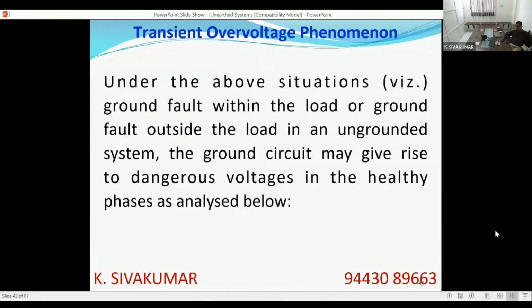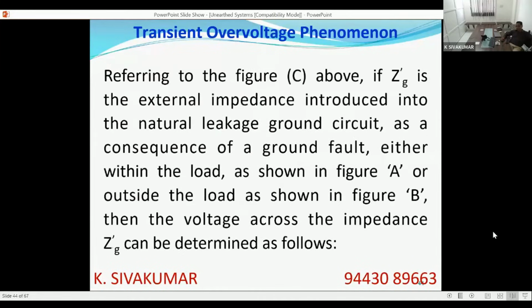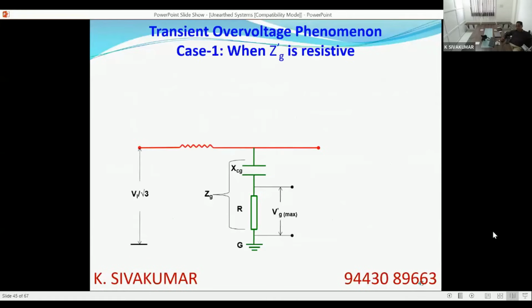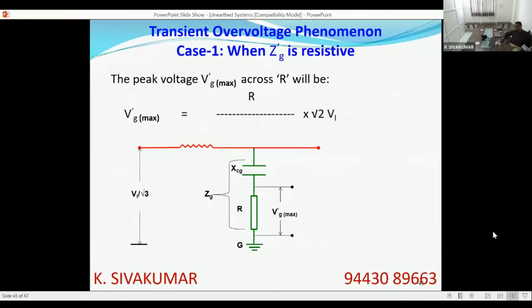So under the above situation, ground fault within the load or ground fault outside the load, the ground circuit may give rise to dangerous voltages in the healthy phases. So the first situation is ZG is the external impedance introduced in the natural leakage ground circuit as a consequence of a fault, either inside the load or outside the load. Then the voltage across the external impedance can be calculated as per this formula.